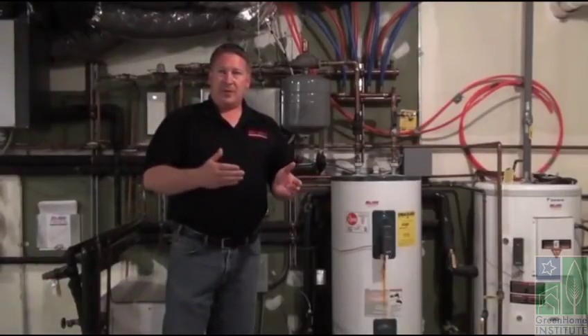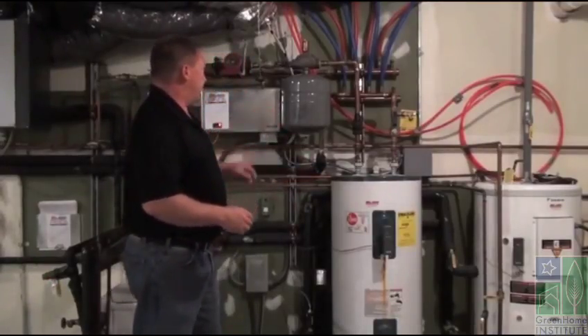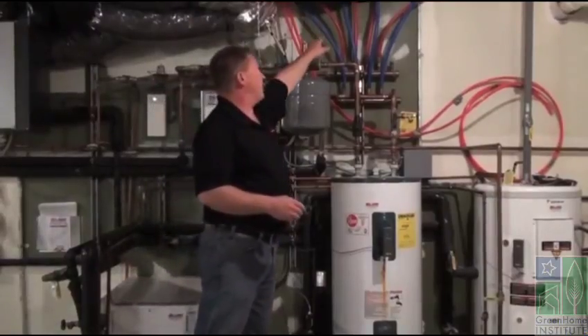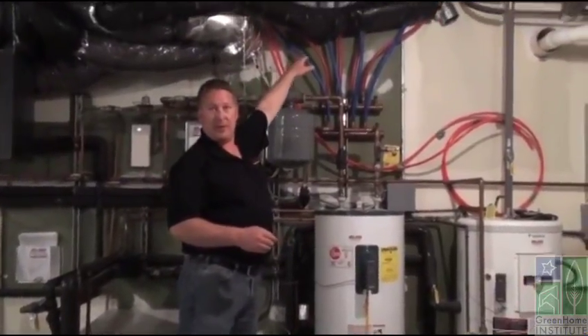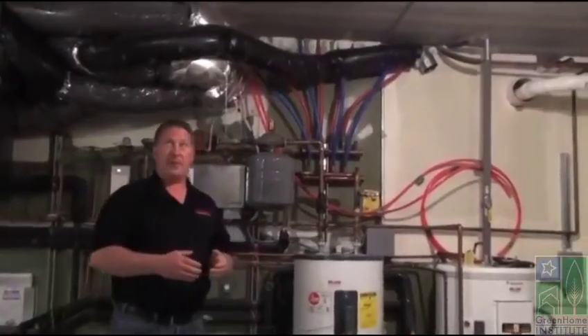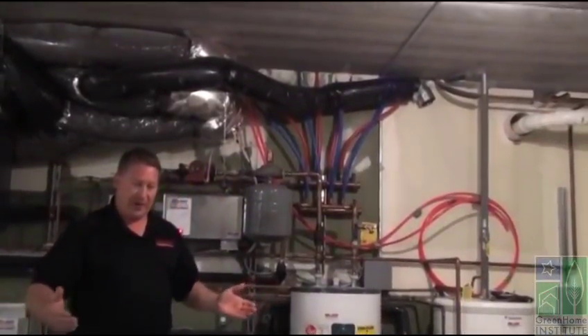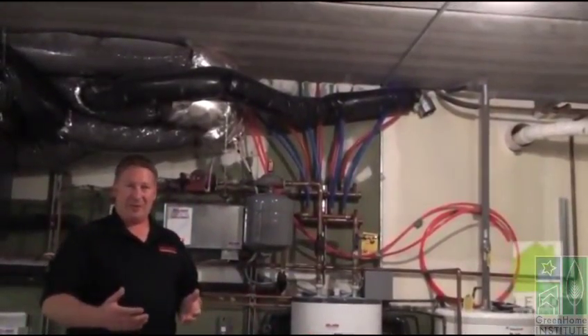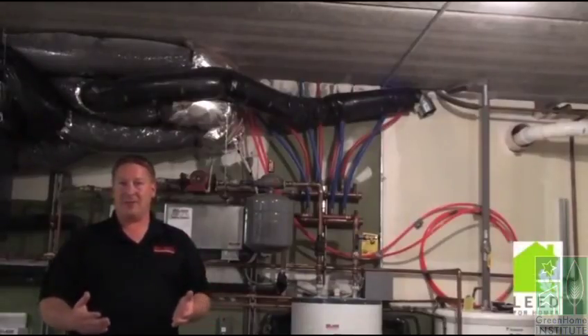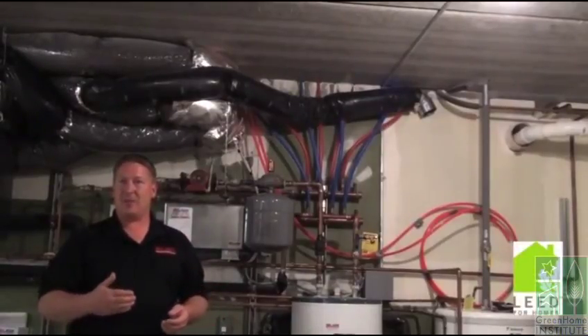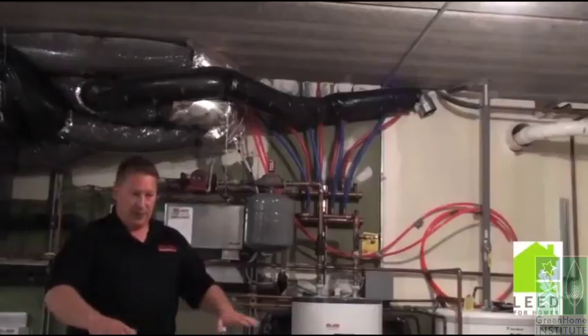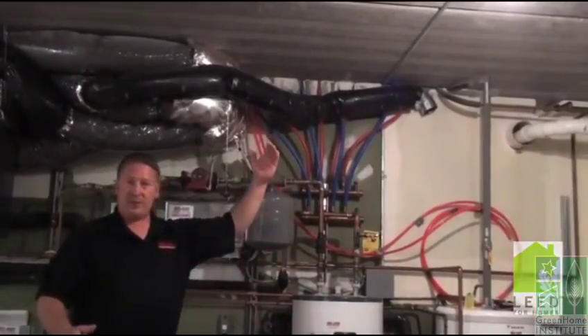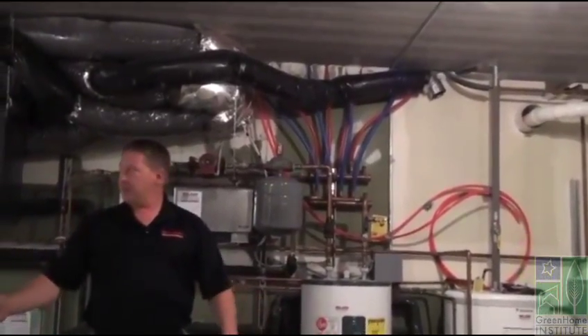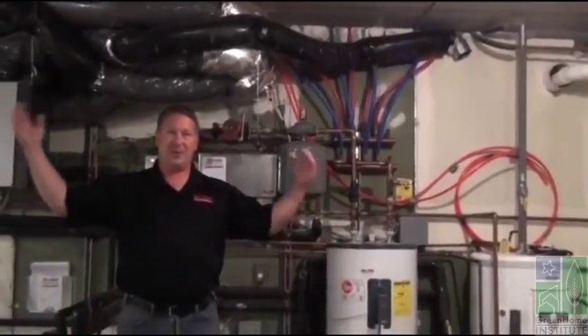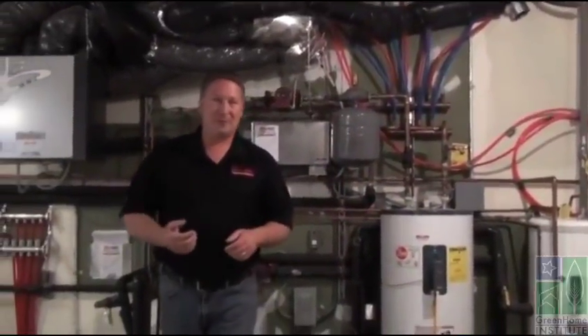So there's no forced air in this house. It's all done by pipes, and you can see some of the tubing that's going up into the concrete floor upstairs and delivering the heat to the floor. And this concrete floor is a large thermal mass, so once you put heat into that floor, it tends to stay there for quite a long period of time, so it doesn't dissipate quickly. You're really not only warming up the floor, but warming up the whole structure as well, because once that heat radiates through the floor, it starts radiating through the walls, and the whole house becomes warm.